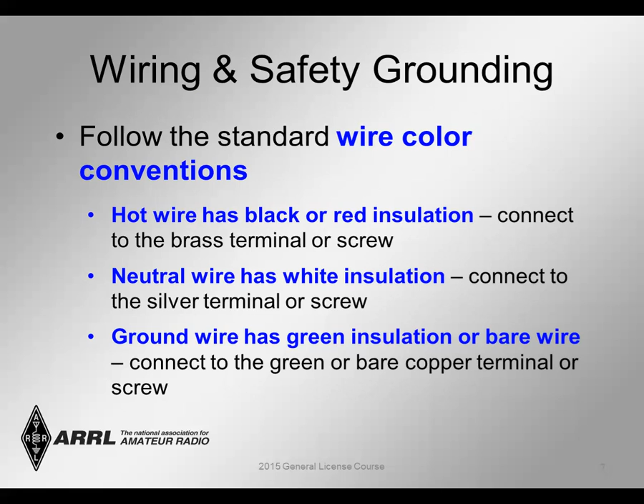is a bare wire. And that bare wire or green wire needs to be connected to the bare copper terminal in, say, a duplex outlet, or in the distribution panel where the circuit breakers are. If the equipment has a metal chassis, which a lot of it does, connect the ground wire terminal to the chassis. What that does is it makes sure that the chassis is at ground, so that if you happen to touch the chassis, you'll be at ground potential and won't get shocked from it.